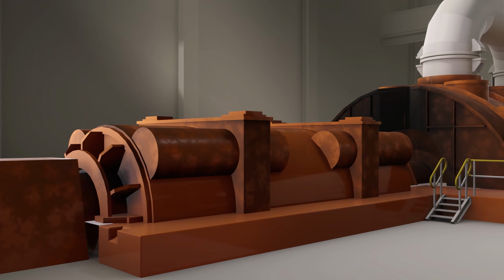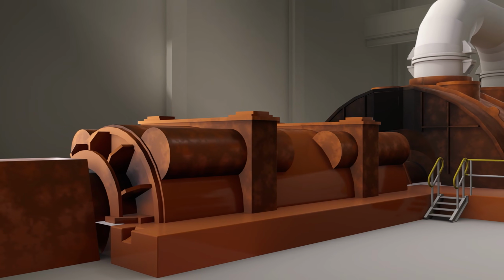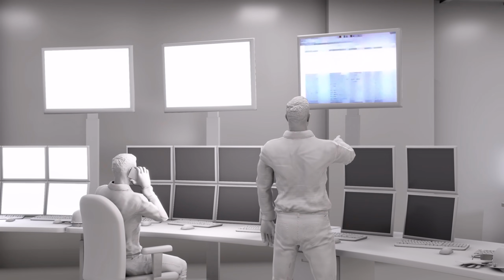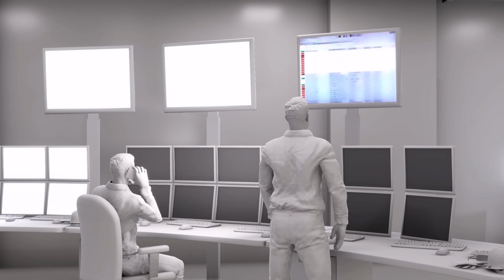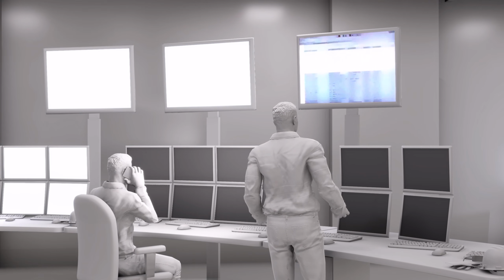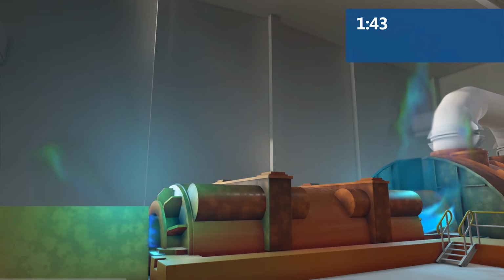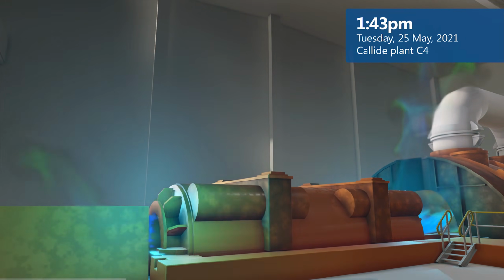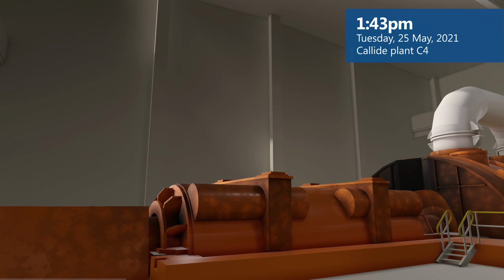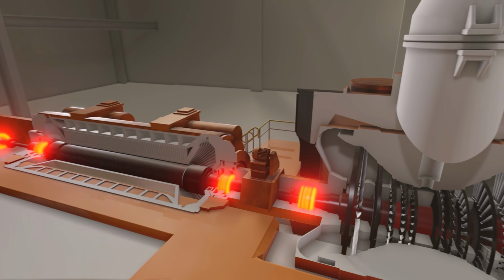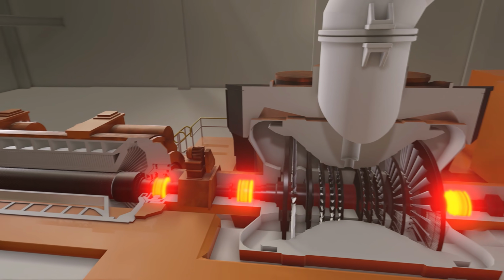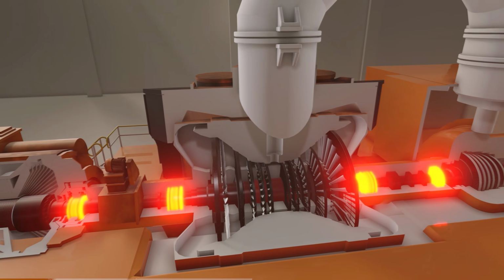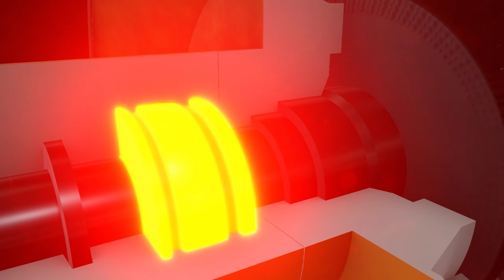Has the boiler tripped? Is steam still driving the turbine? Are they still connected to the grid? But with the screens blank, they have no visibility of what is actually taking place in Unit C4. 10 minutes later, at 1:43 p.m, the generator hydrogen has completely leaked out and the fires at the generator have stopped. But the unit is drawing 50 megawatts and 350 megavars from the grid and continues motoring.